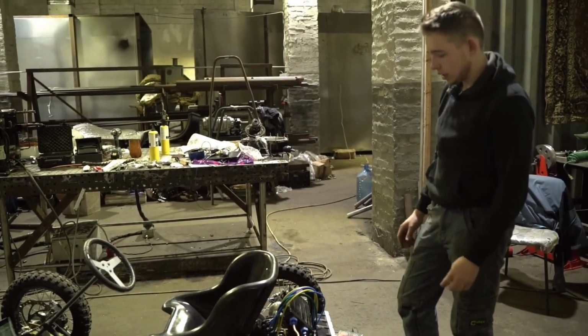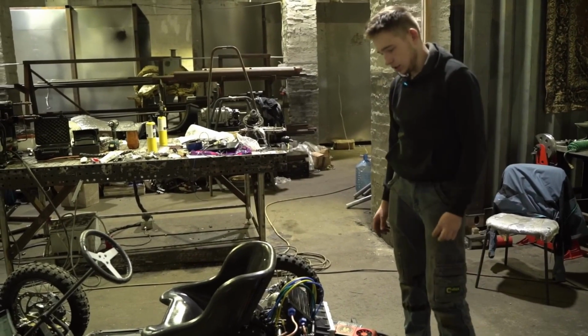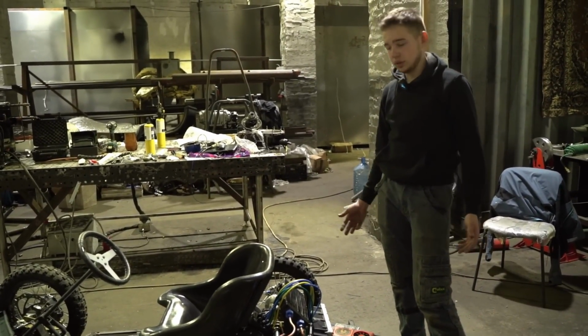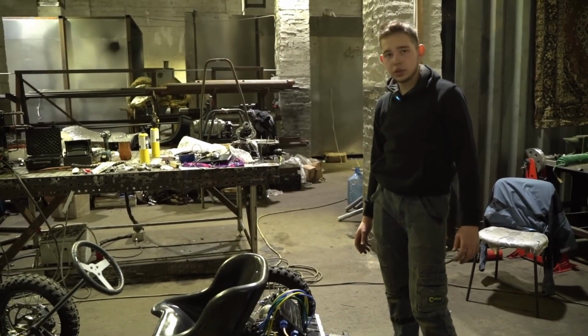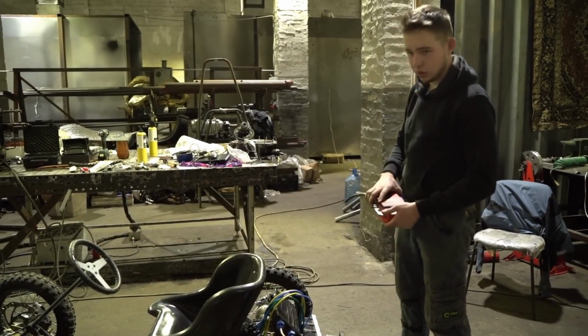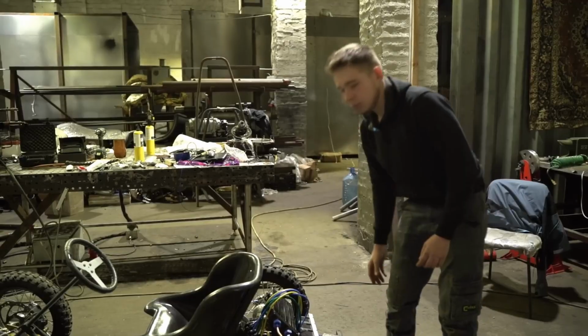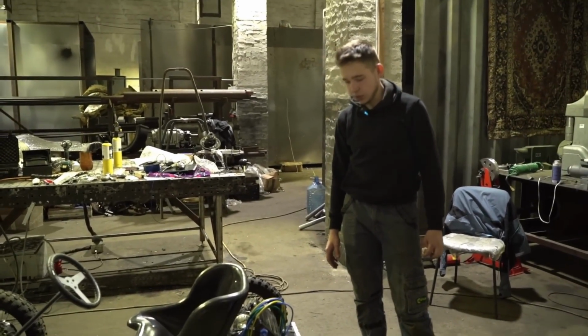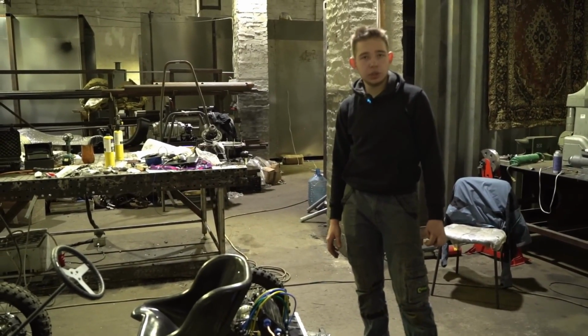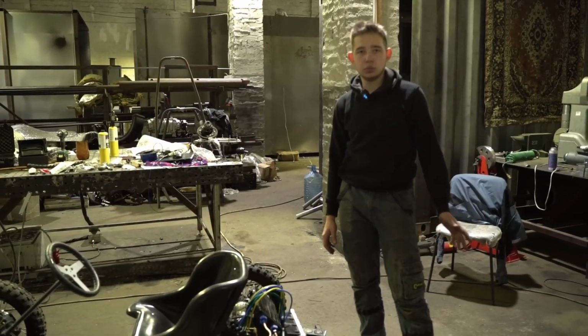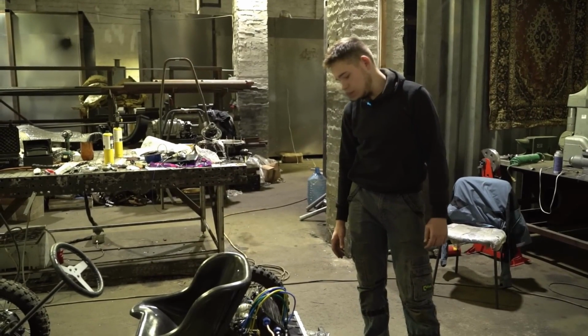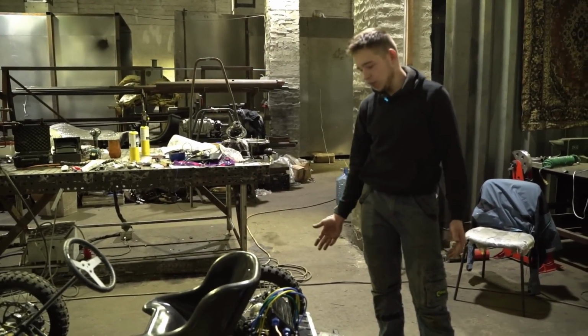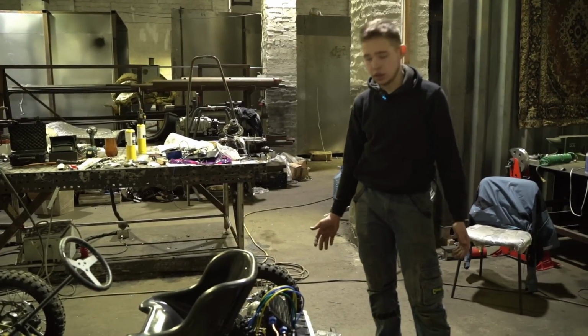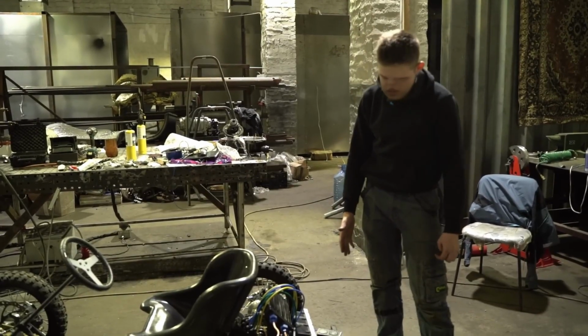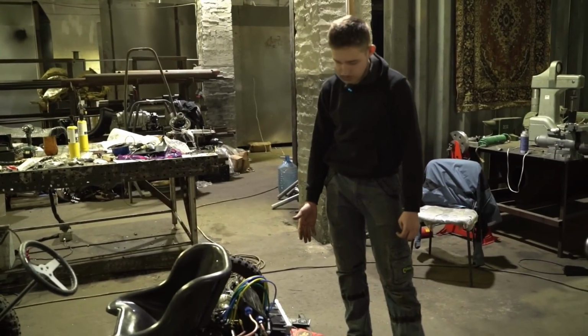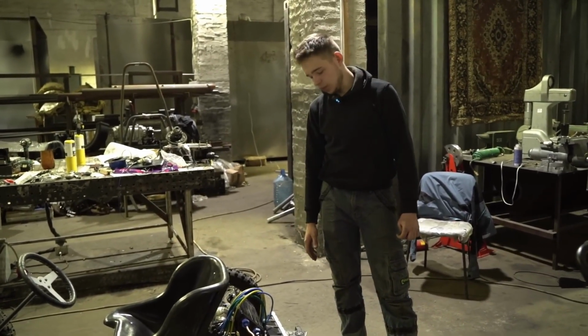Here's the battery, and as for the BMS, we have a very interesting setup. The contactor's negative is controlled by the BMS's power output. The BMS itself is small, like this, rated for 30 amps, and charging also goes through the BMS. What does this give us? Since the currents here are high, peak could really be 400 amps. BMS units rated for such currents are very expensive. For example, we have one rated for 400 amps, which costs about 25,000 rubles. That's a lot. And even if they actually met their specs, that would be great, but in practice, BMS units labeled for 200 amps burn out at a constant 100 amps, not peak but continuous, so it's unclear what rating you really need. If our nominal current is 300 amps, do we need a BMS rated for 1000 amps?